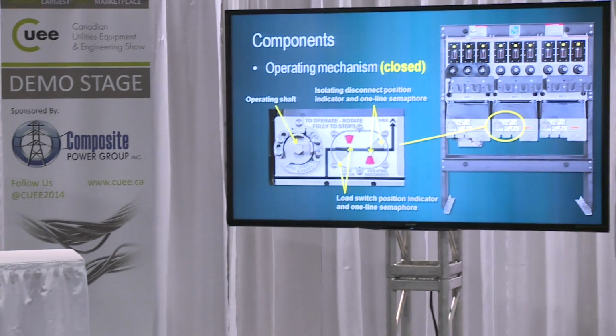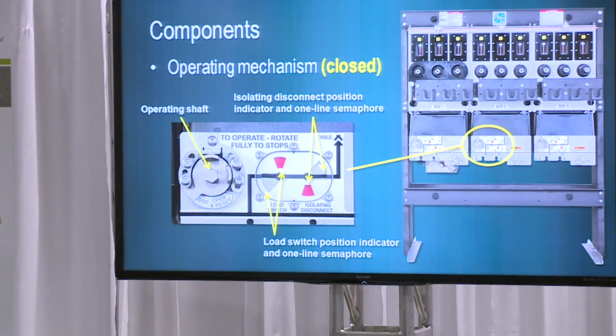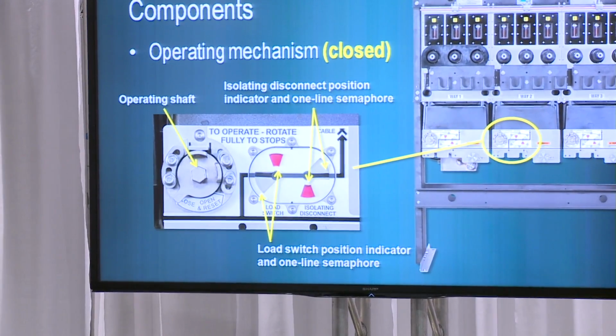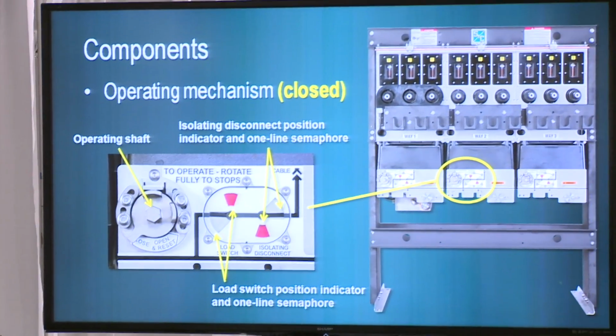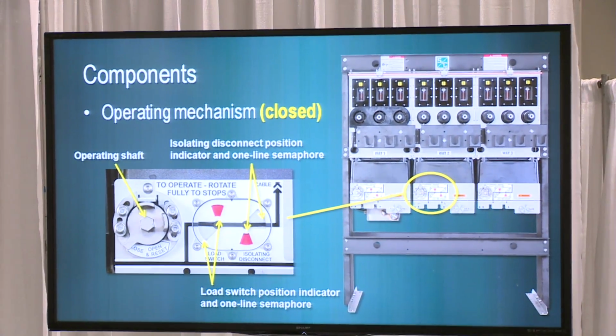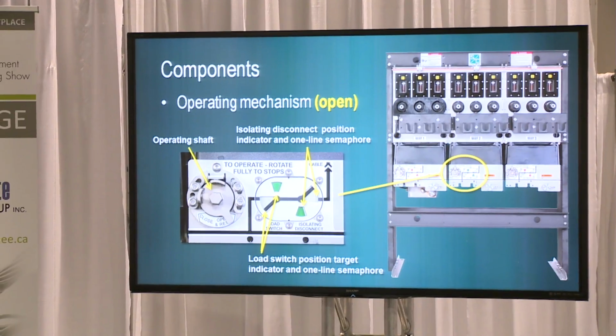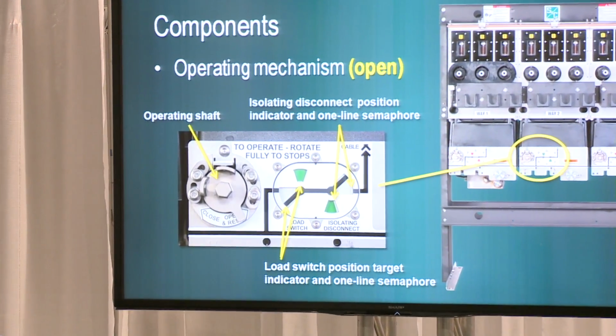We spent a lot of time, as I mentioned a moment ago, on the state indication. So here you see 2 ways to tell that this is in the closed position. You see the red target. Red means closed, and in a second I'll show you green is open. And you'll see that there's a mimic bus with the semaphores, and those flags will move to show that it's in the open position. So this is closed, and this is what open looks like. Now the third way to tell if it's open is to look at the visible open gap, the isolating disconnect, and I have a picture of that in just a second.